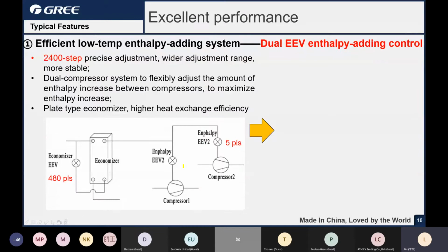And next one, let's have a look at the expansion valve. For the GMV6, there are many different expansion valves. So the first one here, you can see this is the economizer expansion valve. It is 480 pulses. And for every compressor, there is an EVI, enthalpy injection valve. So this is another expansion valve, but this expansion valve is just 5 pulses.